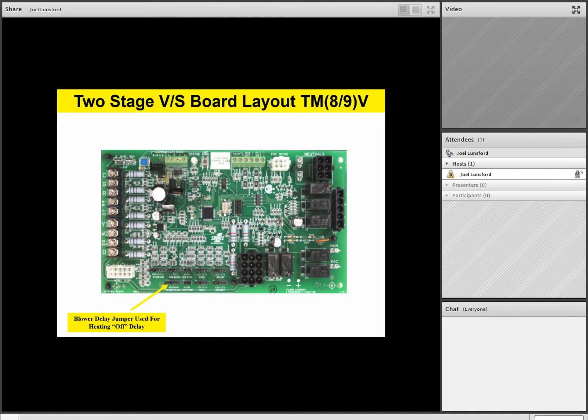So we typically ship that around 100 to 120, but it is field selectable from 60 to 180 seconds on the product. And then finally, we have a staging jumper. Unlike our previous control board that had an auto function, this does not have an auto function. It's strictly timeout. So if you're stuck with a single stage thermostat, we can still give you some staging with a two-stage variable speed control board, but it's strictly timeout: 10, 15, or 20 minutes.